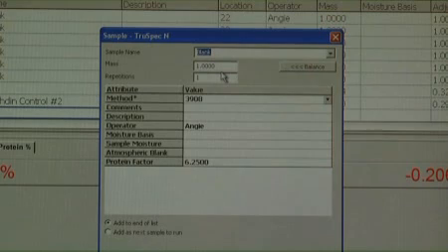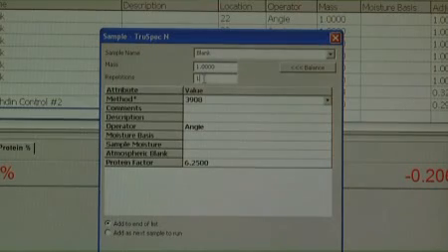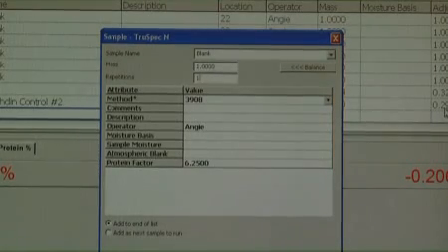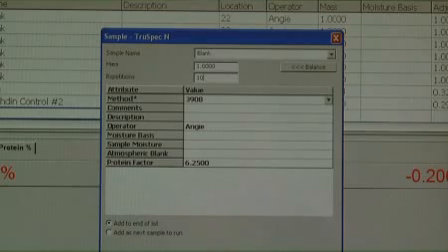Leave the default value in the mass box at 1.000. In the Repetitions box, type the number of blanks to be analyzed. This number should be sufficient to obtain 3 consistent blank values once the instrument is conditioned. Approximately 10 blanks will normally satisfy the minimum requirements for conditioning and setting the blank nitrogen area.